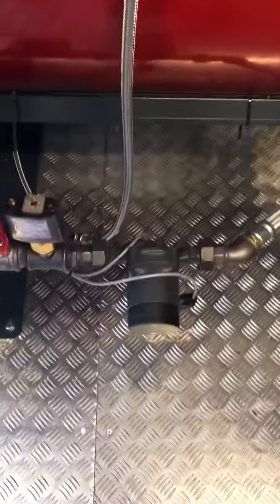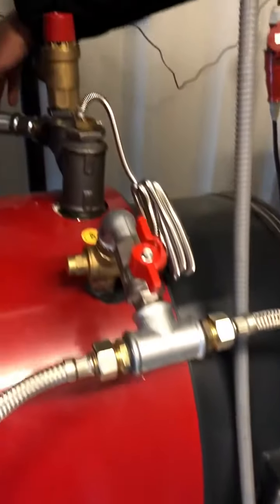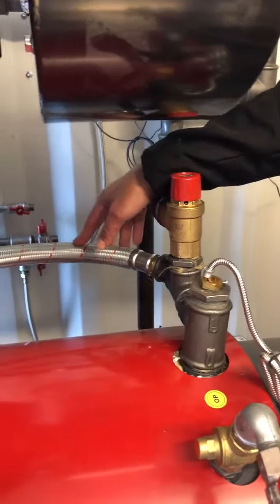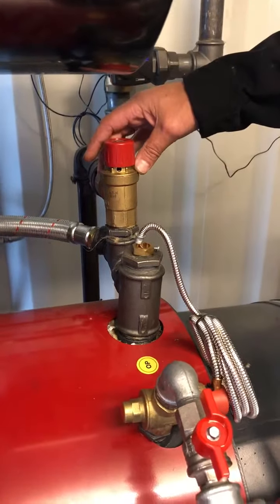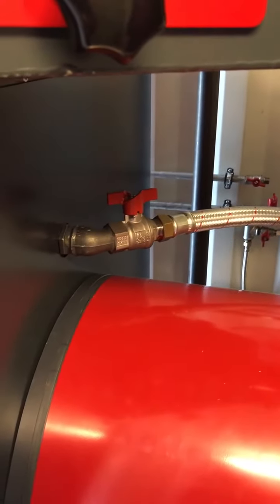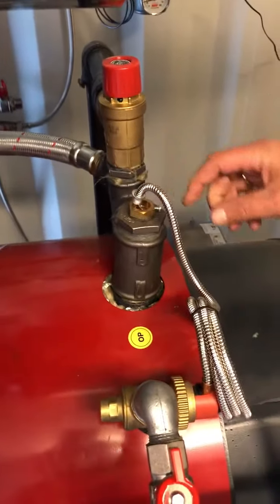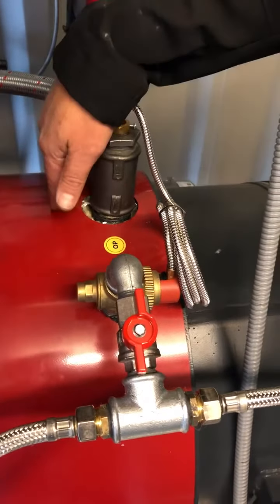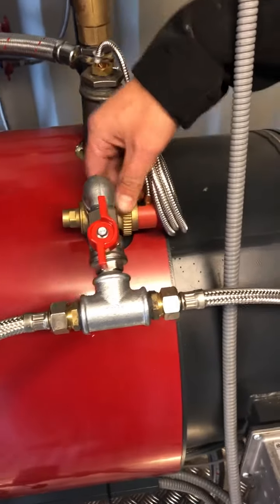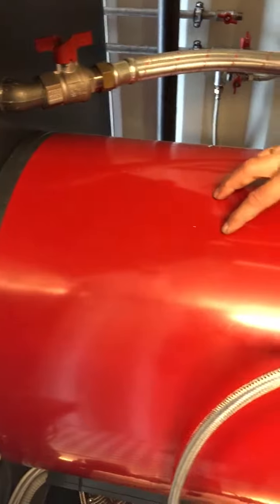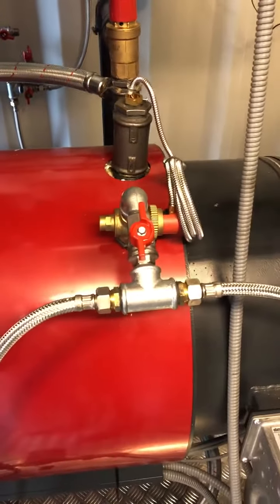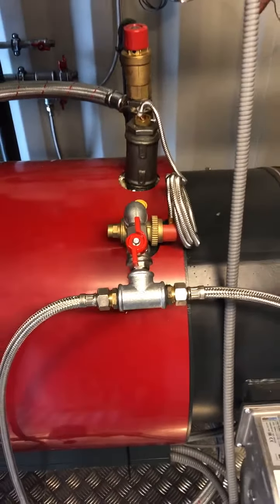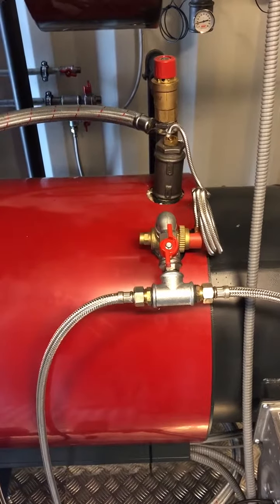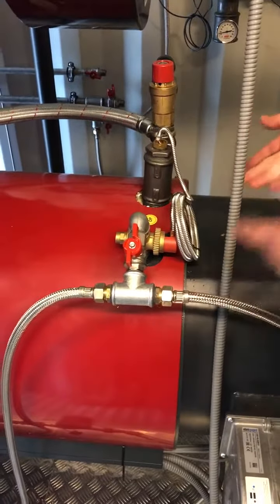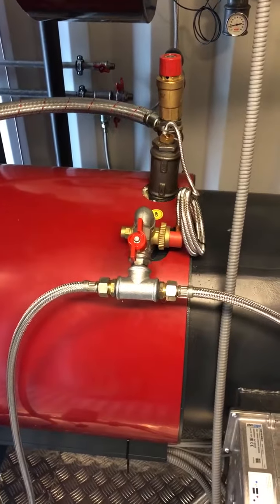We have a safety valve here, so if the pump stops working or the 2 flexible hoses here get stopped with some heavy thick boiler water, you have this safety valve for safety, or when somebody closes the valves. And then we also have a sensor here in the top of the burner tube in the small water chamber that feels if the temperature gets too high in the water. This sprinkler valve will open for water through a cooling coil placed in the water chamber of the burner tube. If this one opens for protection of the water chamber, the water outlet is in the bottom, 180 degrees in that direction. The water comes out. And if it has been in function, it has to check that the valve has closed again and no water is dripping out on the outlet.